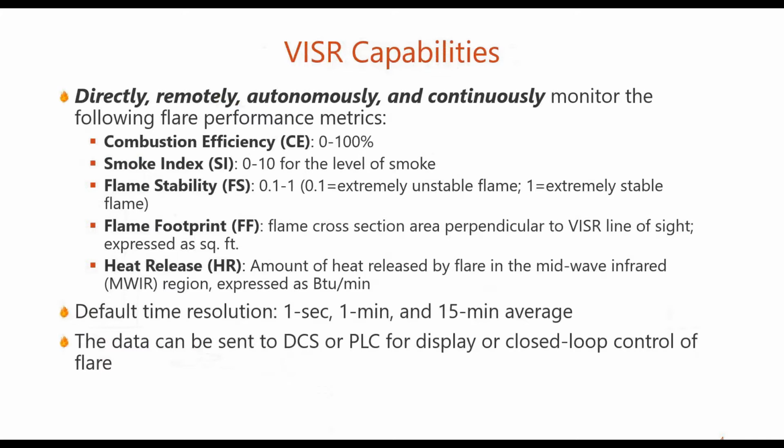Flame footprint is simply a cross-sectional area perpendicular to the VISR line of sight, which represents the combustion plume. It's typically larger than the visible plume if the flame itself is visible. This is really looking at the flame and the post-combustion gas.